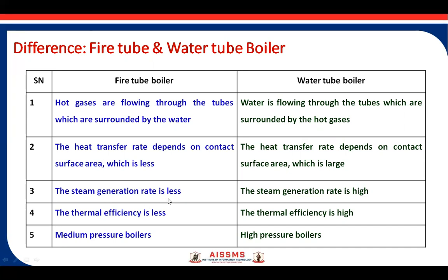Steam generation rate is less in fire tube boilers as the surface area is less, but in water tube boilers the steam generation rate is higher. In terms of efficiency, the thermal efficiency of fire tube boilers is less and that of water tube boilers is higher. Fire tube boilers are used for locomotive or marine applications as medium pressure boilers, while for power generation in thermal power plants, high pressure water tube boilers are used.